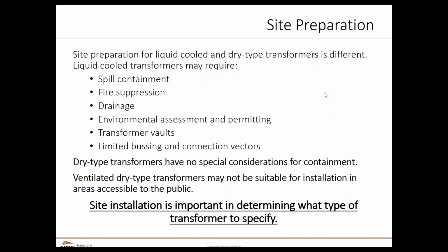Site preparation is a big one. With liquid-filled transformers, there might be things like spill containment, fire suppression, drainage, environmental assessments and additional permitting, transformer vaults, limited busing and connection vectors that will result in some differences in design that may not be any consideration or any issue for a dry type.